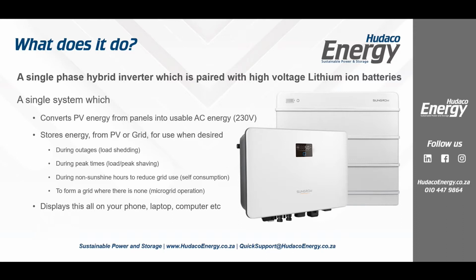The second thing is during peak times, we can do load or peak shaving. So we can discharge battery power to number 1, help the country and ease the load during those peaks. And number 2, especially if you're on a time of use tariff for whatever reason, we can cut that down. The third thing it does is during non-sunshine hours, it reduces your energy imported from the grid.